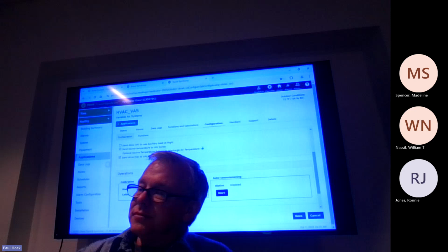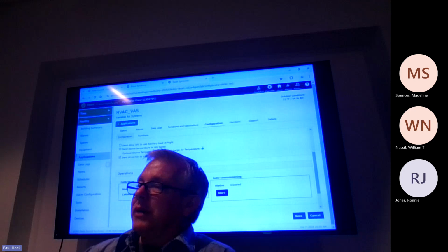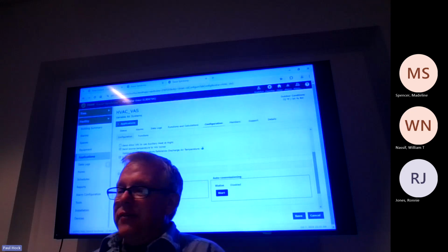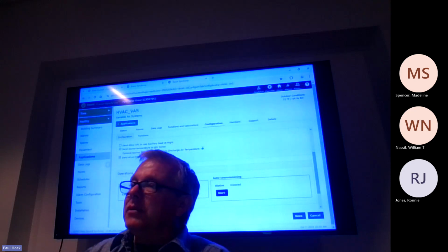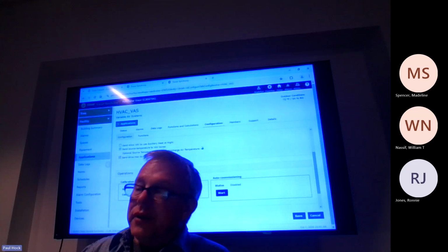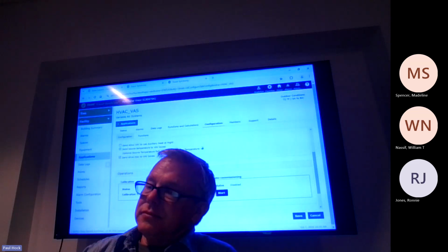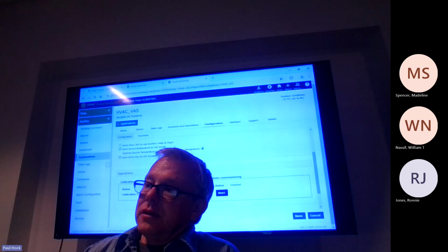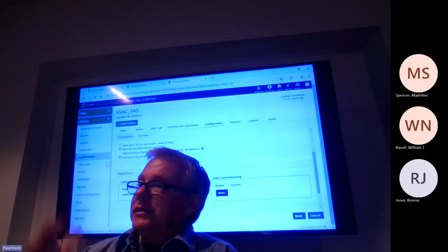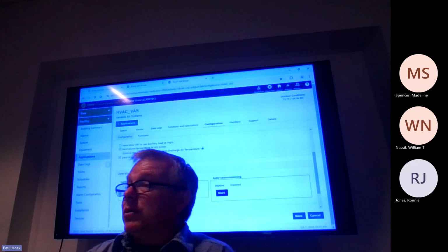I guess if it found something that was not calibrated, normally it would send out an alarm. Yeah. So, like I said, if one of the boxes, the airflow is not reading, you'll get an alarm. Would that be the first thing to try to correct it? I guess there's not like a... There is something you can do. Or is it just change the time or something? Would that get it to try and recalibrate? Like, you could override it to 0 just so that it knows where 0 is and release it and see if that works. Sometimes that works.